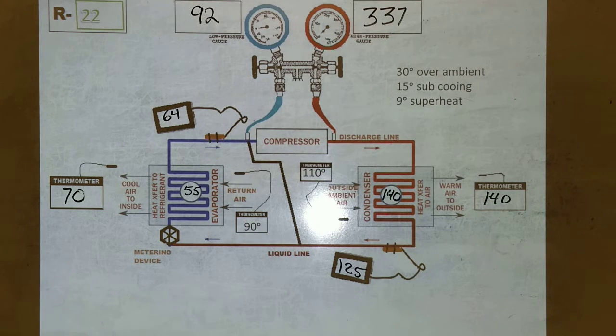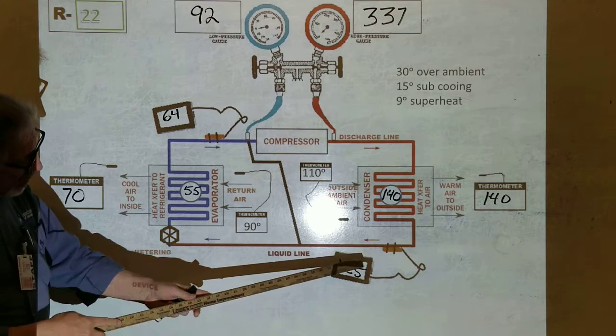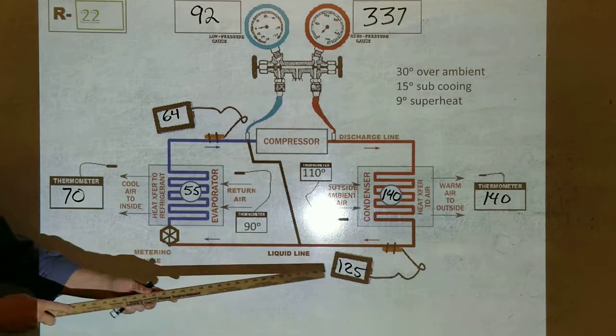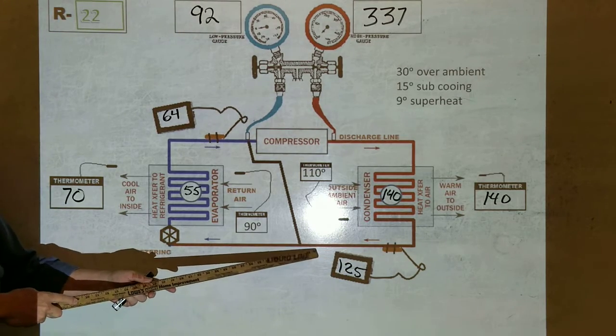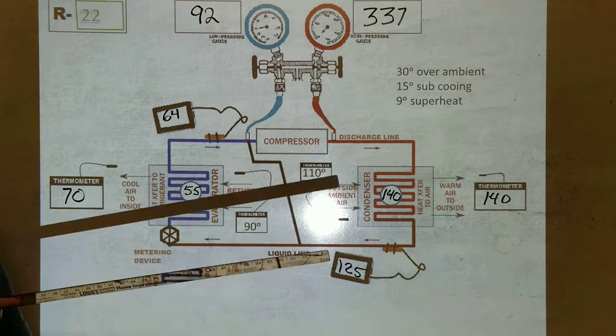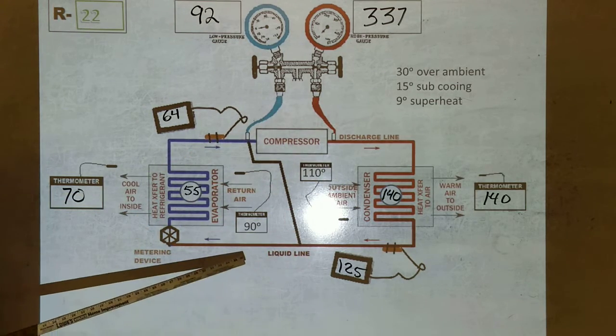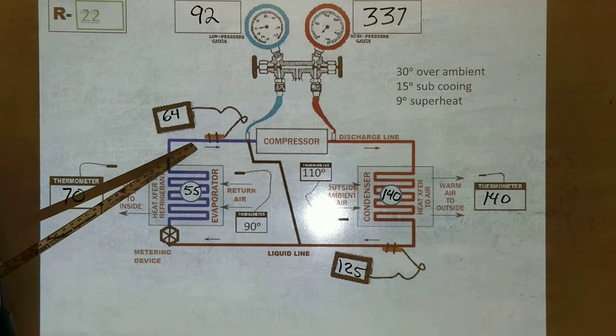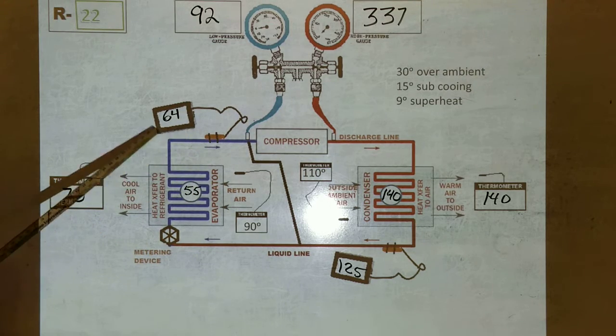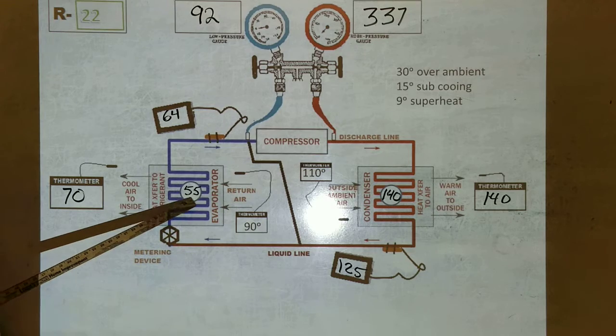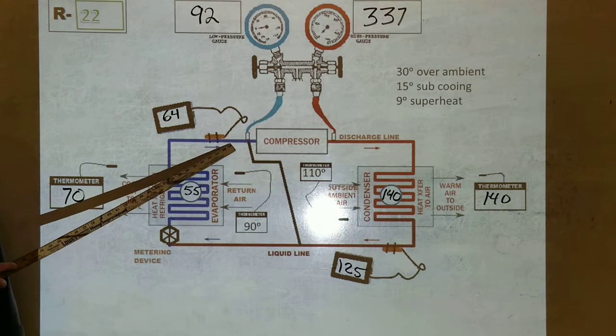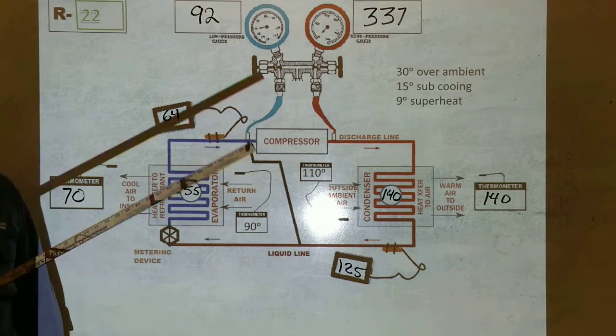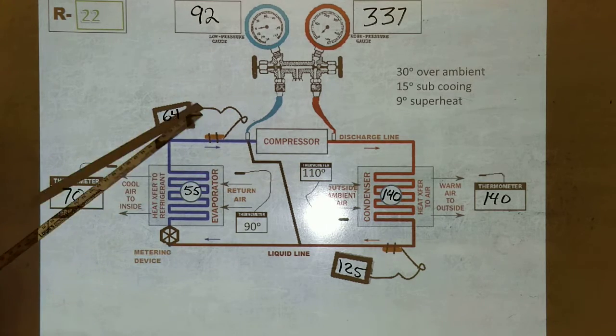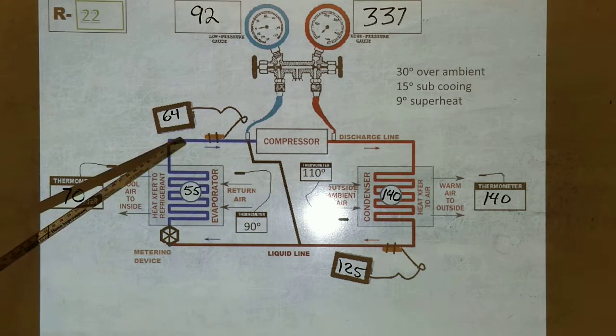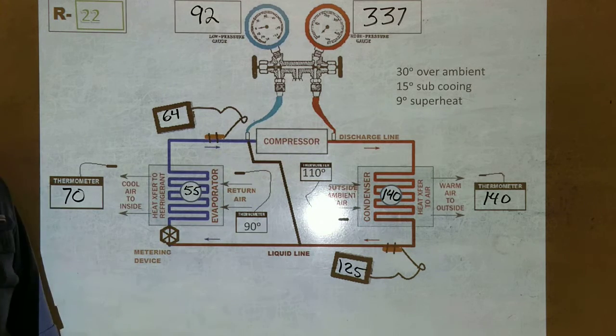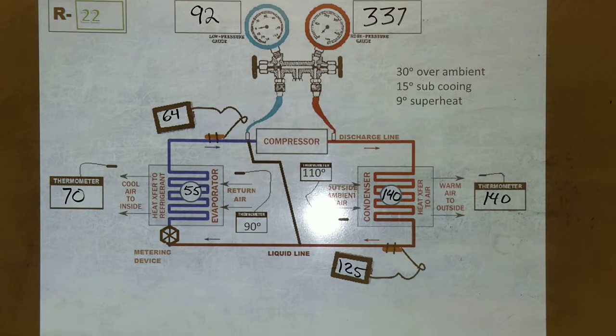And the reason we do that is because it's going to give us a better idea of what's happening inside that system. So at 125, I know that there's 100% liquid in that line. That's telling me there's 100% liquid in there without having to see inside of it, because it's copper, you can't see through copper. Same thing with the suction line. That temperature is telling me that is 100% vapor. It's also telling me the difference between these two temperatures is the superheat, and it's telling me what's going on in the system.